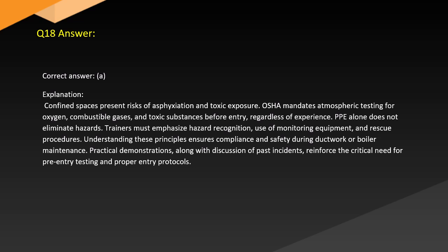Answer. Explanation. Confined spaces present risks of asphyxiation and toxic exposure. OSHA mandates atmospheric testing for oxygen, combustible gases, and toxic substances before entry, regardless of experience. PPE alone does not eliminate hazards. Trainers must emphasize hazard recognition, use of monitoring equipment, and rescue procedures. Understanding these principles ensures compliance and safety during ductwork or boiler maintenance. Practical demonstrations, along with discussion of past incidents, reinforce the critical need for pre-entry testing and proper entry protocols.